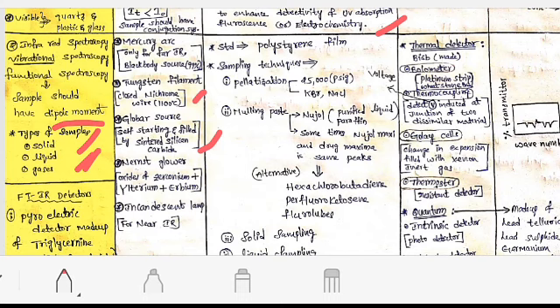Nernst glower is made up of oxides of zirconium, yttrium, and erbium. Incandescent lamps are used for near IR. The standard used in IR spectroscopy is polystyrene film. Sample techniques include pelletization where we apply 25,000 pressure and use KBr or sodium chloride as a medium. Mulling paste is also used where we use nujol, which is purified liquid paraffin or mineral oil. Sometimes nujol maxima and drug maxima are the same, so as an alternative we use hexachlorobutadiene, perfluorokerosene, and fluorolube.